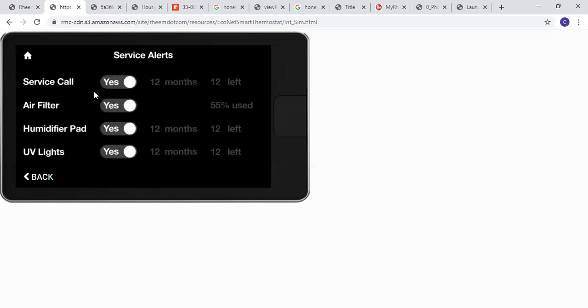Alerts, you can turn your service call, say every 6 months. Air filter, it will do an automatic air filter check every day at 9 a.m. You can change that time if you need to, but every day it's going to check that. So it's going to set a baseline for your static pressure. So if, for instance, you have a really dirty filter, it's going to tell you to change your filter.